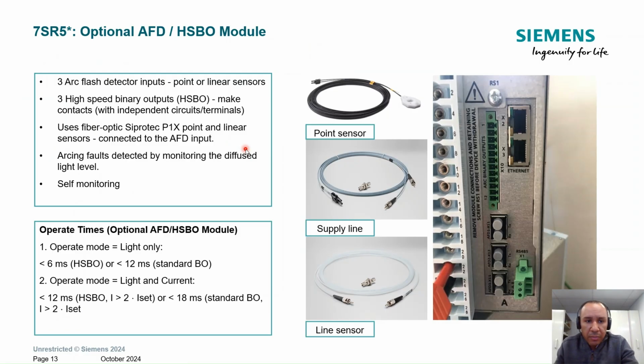As I mentioned, this device is capable of performing arc flash, and this is the arc flash card, together with the comms card. For the comms here, you have the option for RJ45 or fiber. When you select the device, you need to set which type of connection you're going to use for the Ethernet connection, either RJ45 or fiber. Also, you have the option for serial communication if you're going to use Modbus, DNP3 or IEC 103. And for the arc flash, when you select the relay, select the part number of the relay.